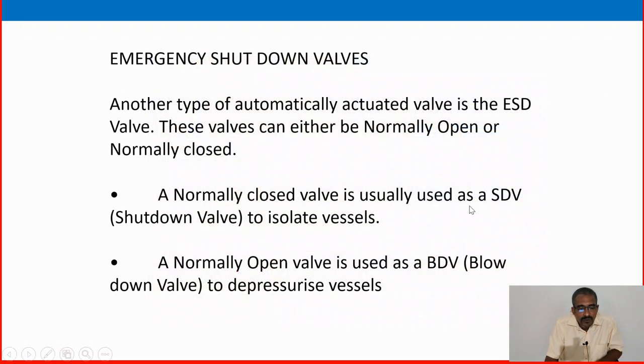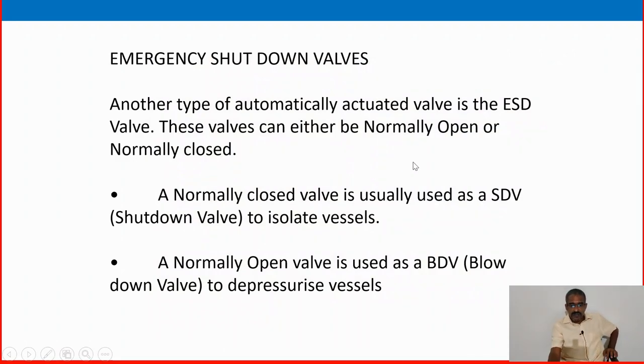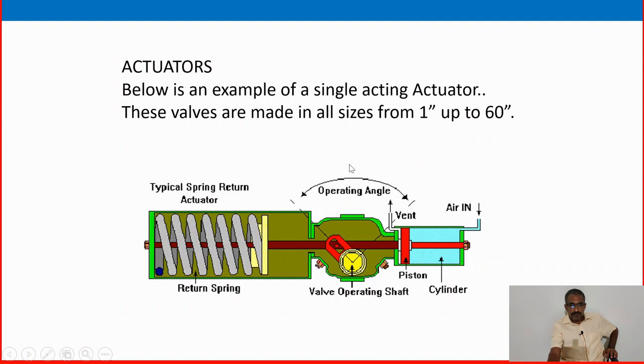Emergency shutdown valves are another type of automatically actuated valve — ESD valve. These valves can be either normally open or normally closed. A normally closed valve is usually used as SDV — shut down valve — and the other one is a BDV — blow down valve. Below is an example of a single acting actuator. These valves are made in all sizes from one inch to 60 inches.